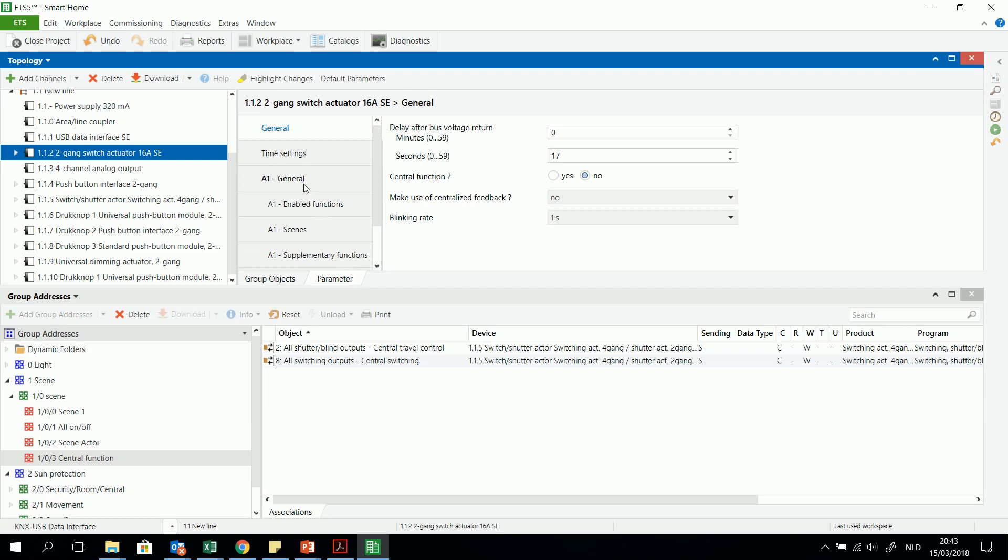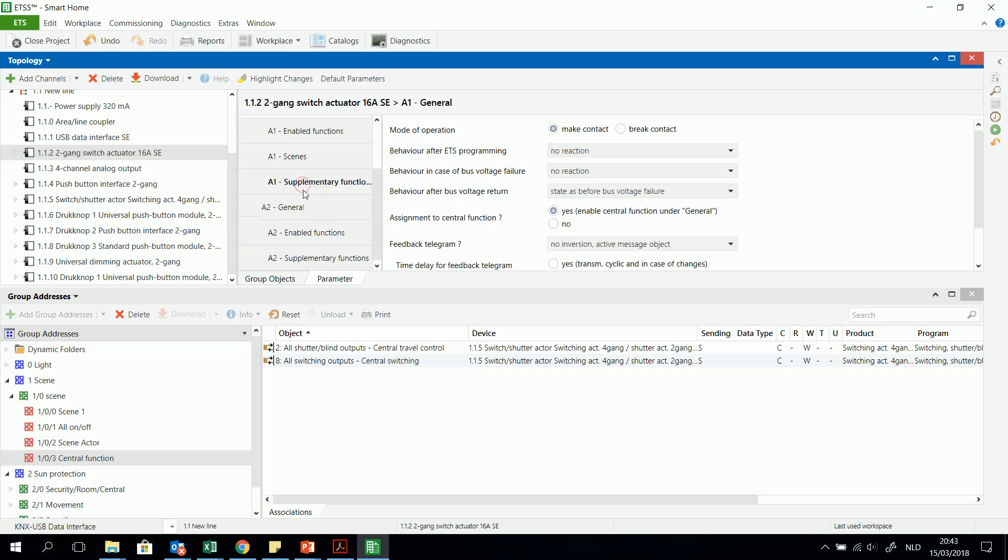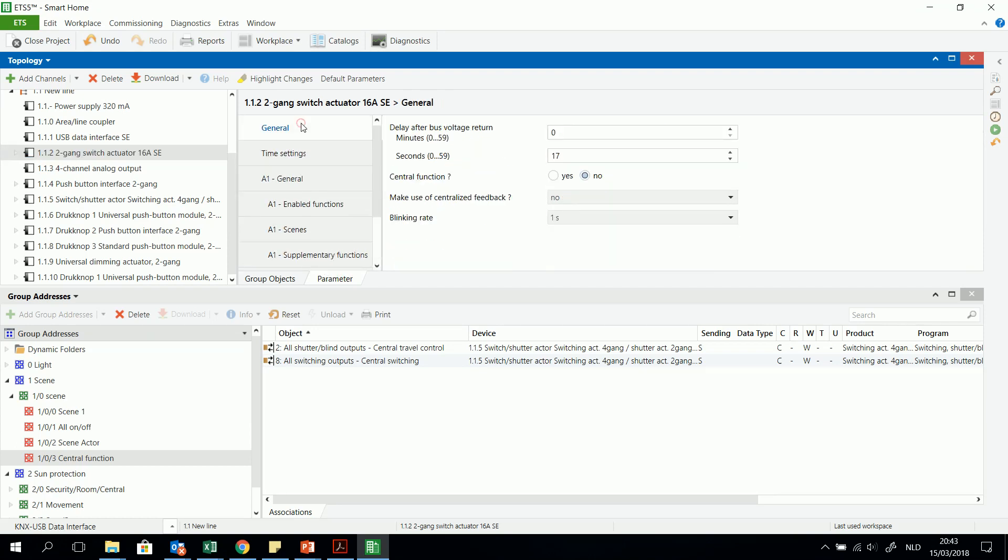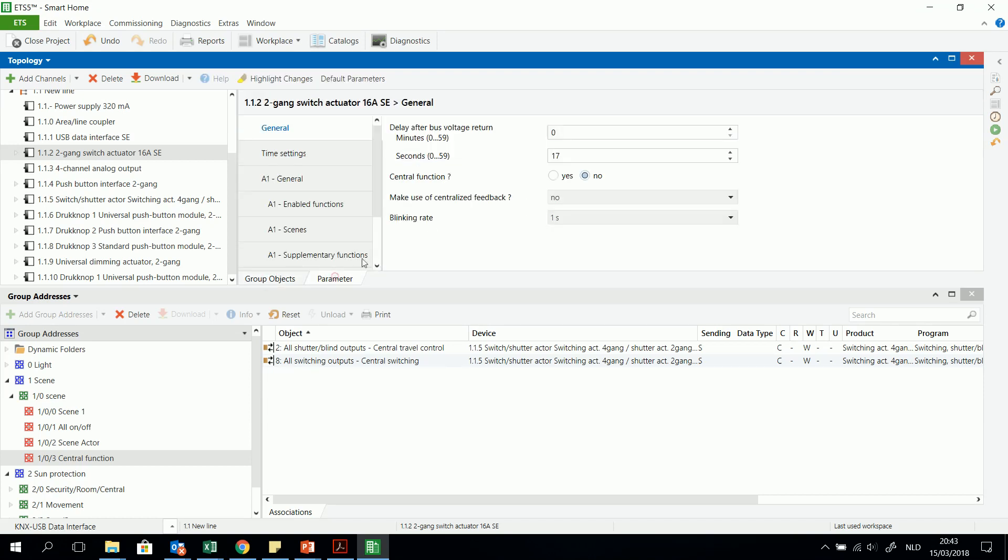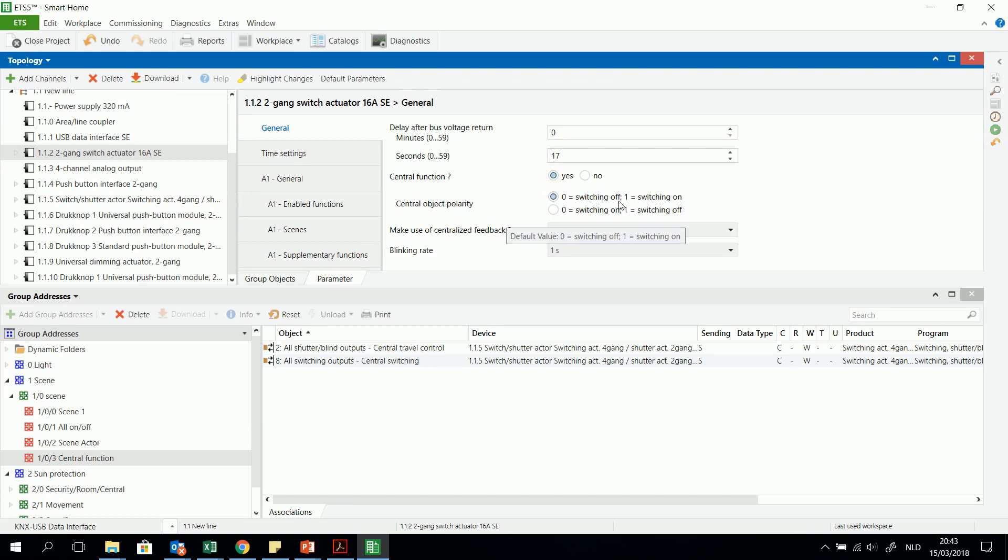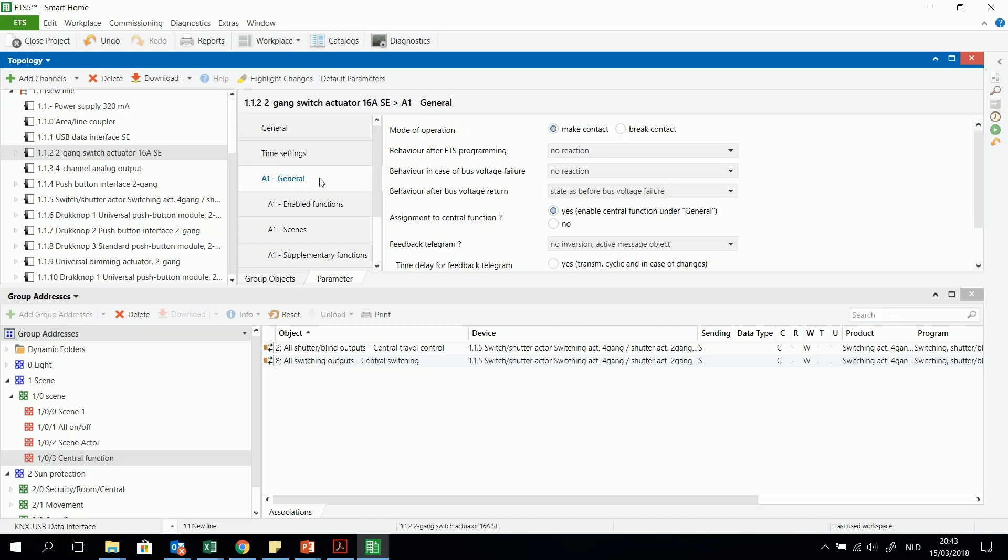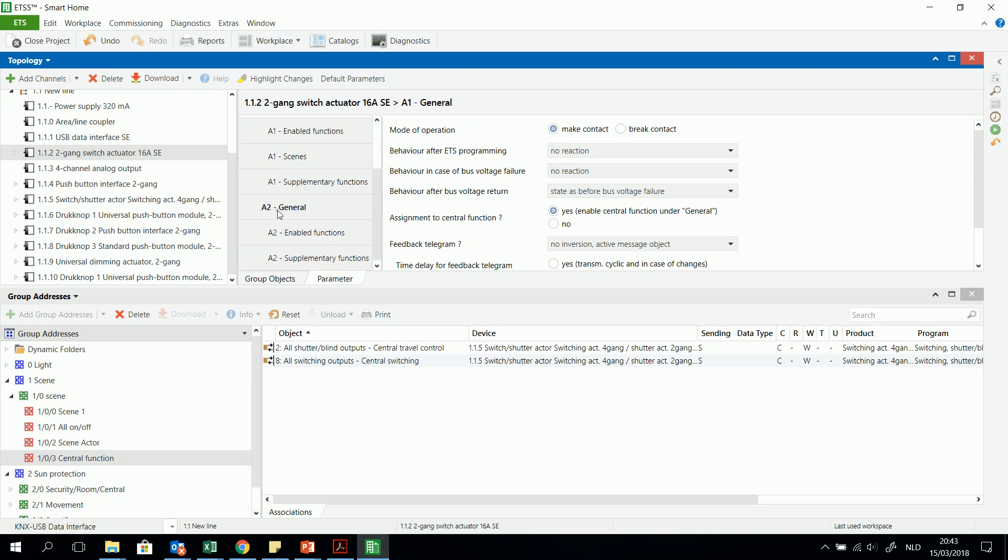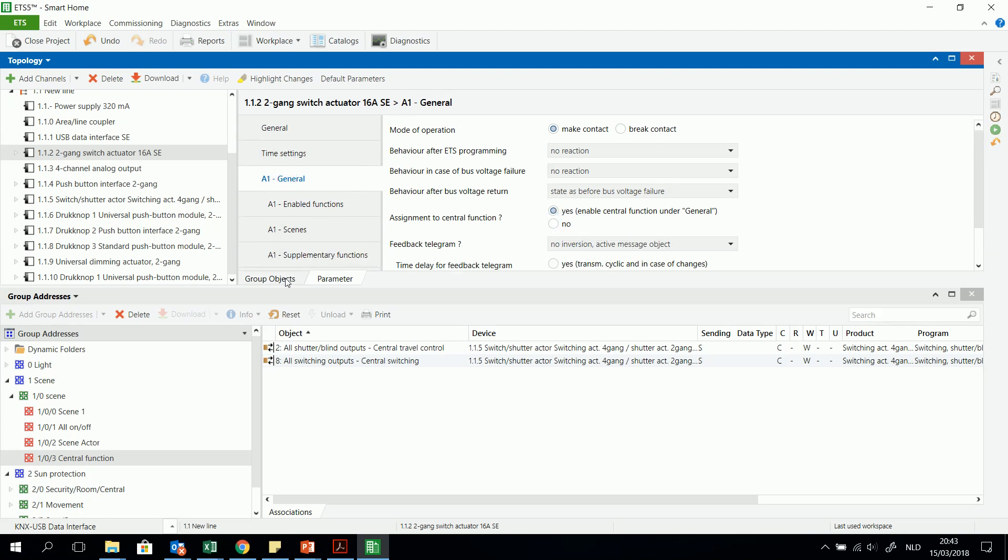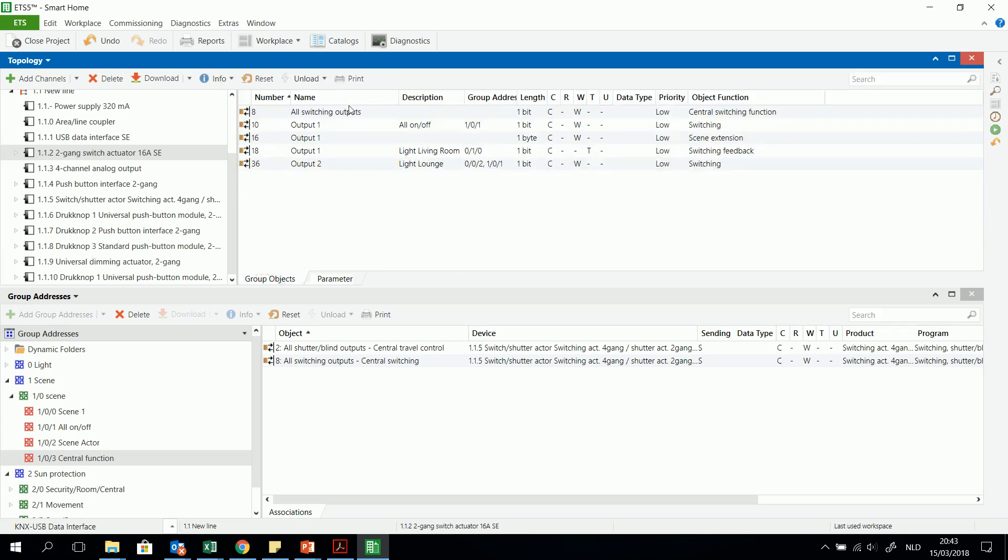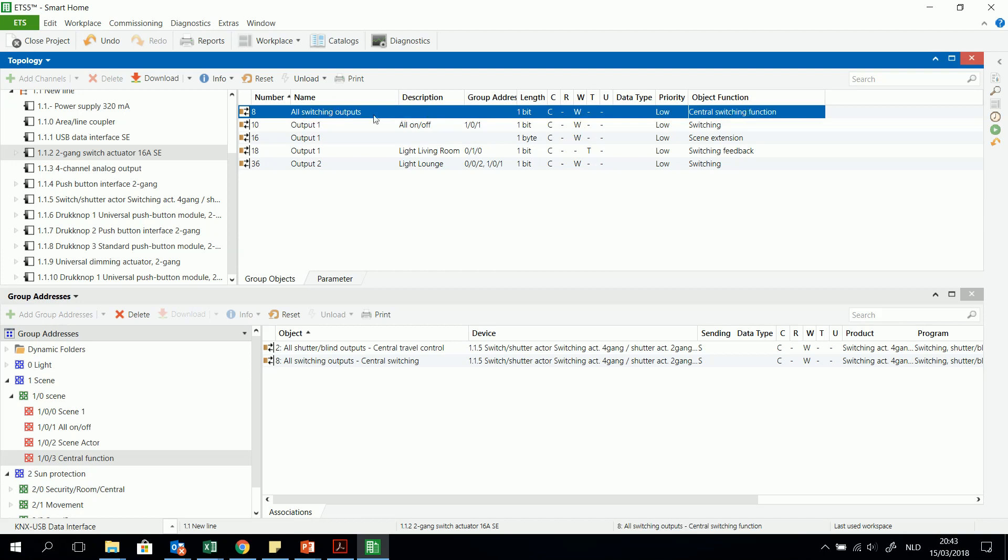I have here two outputs. And again I have to look, can I activate the central function. For this moment in the group object there's no central function at all. And then I will activate this. I have to choose what's the reaction on a one or on a zero. I will take this option. And then again to the different channels I still have to activate them, assign them to the central function. For a one and a two, for example I will leave this on no. So only the A1 will receive a one or a zero through the all switching output central switching function object of one bit.